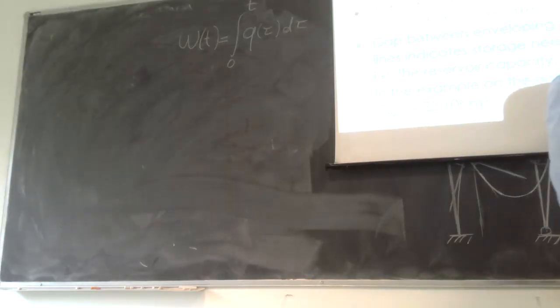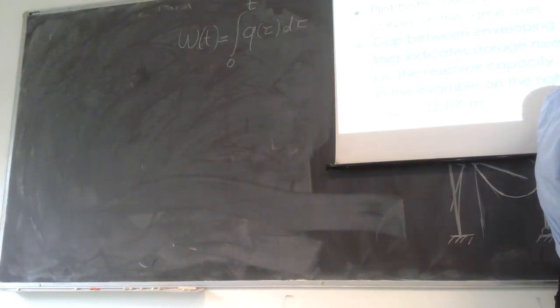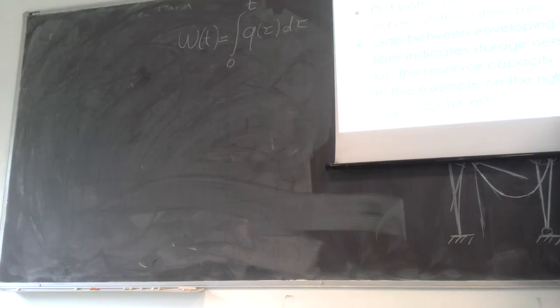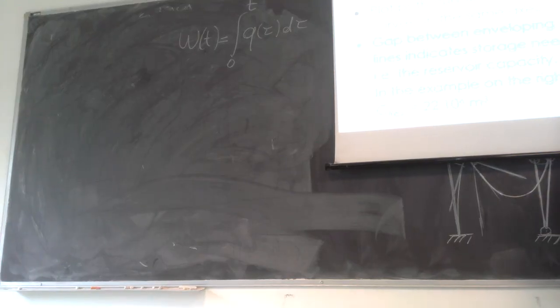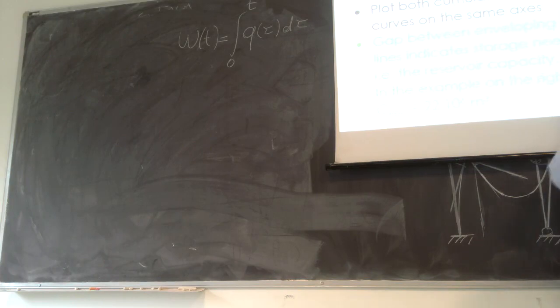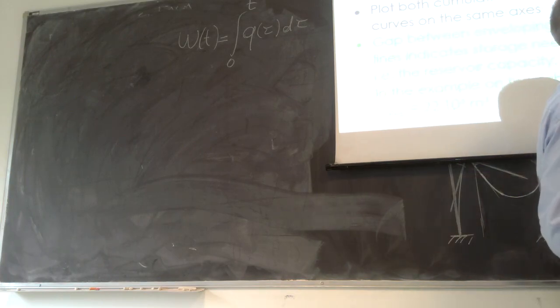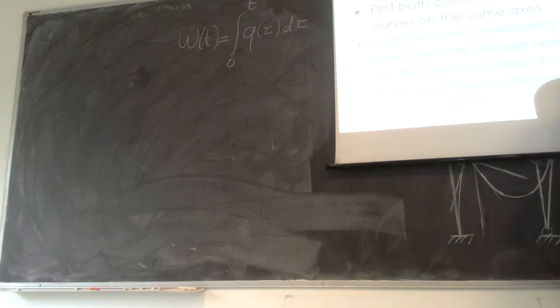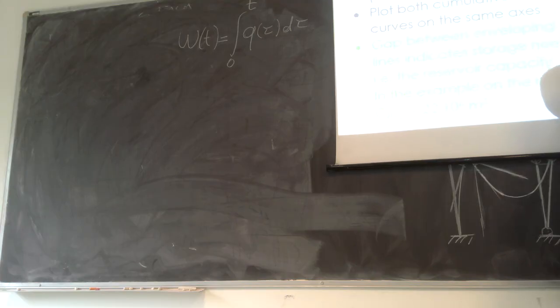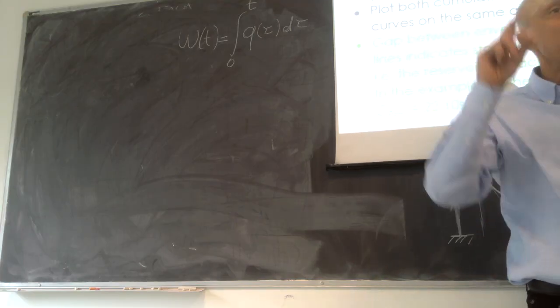Yes, we'll see this over and over again. What I just said is that you take the mass curve of the turbine flow, the green line, you move it downward until it touches the black line, which is the inflow coming into the reservoir, removing the environmental flow, which we cannot use. Then you do the same upward. You shift this curve upward until it becomes tangent, and the distance between the two is the active capacity of the reservoir. Why?